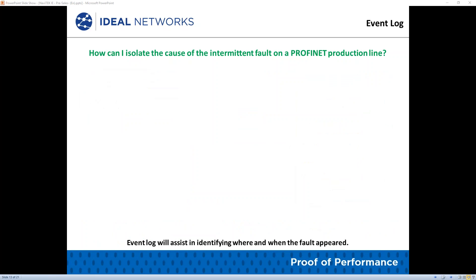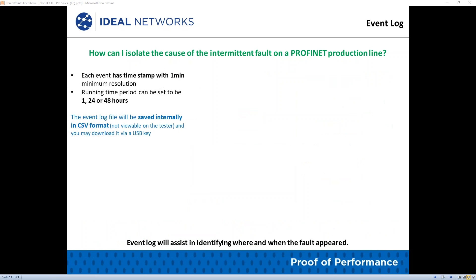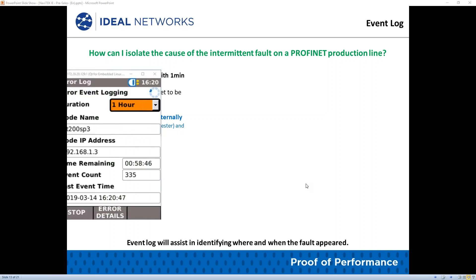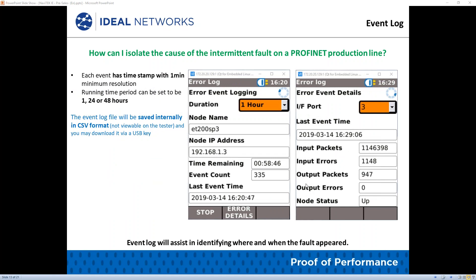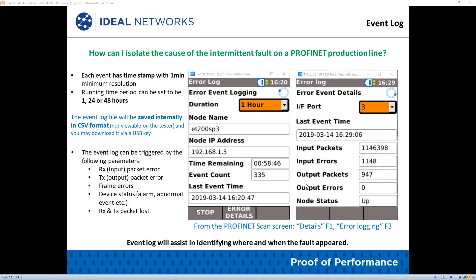You can also find intermittent issues with the event log. Each event has a timestamp with a one-minute minimum resolution, and the running time can be set to 1 hour, 24 hours, or 48 hours. The event log file is saved internally in CSV format and can be downloaded via a USB key.